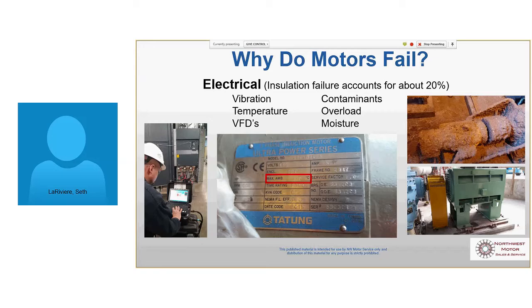That's a little Baldor motor. There's a customer down in Longview. They were failing this motor every 3 weeks. That's as long as it lasted. And you can see why. So the solution there, and I'm not trying to throw Baldor under the bus, but that was just a standard Energy Saver Baldor motor, okay? Cast iron, rolled steel, their lowest quality. So it was an upgrade to their cheapest product, but it just didn't survive.